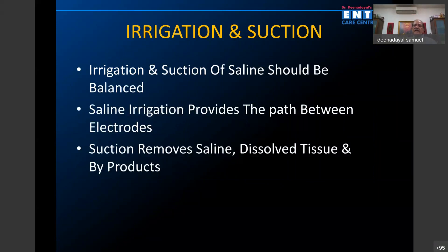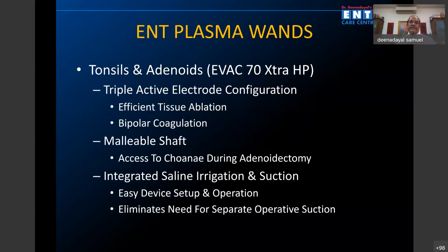Irrigation and suction of saline should always be balanced. The saline irrigation provides the path between electrodes — when saline irrigation is less, coblation will not be at its optimum. Suction should be sufficient to continually remove the saline and dissolved tissue and byproducts.